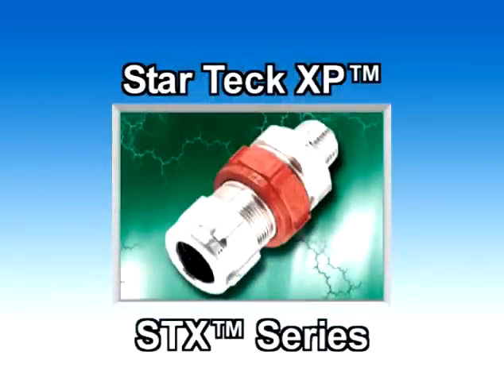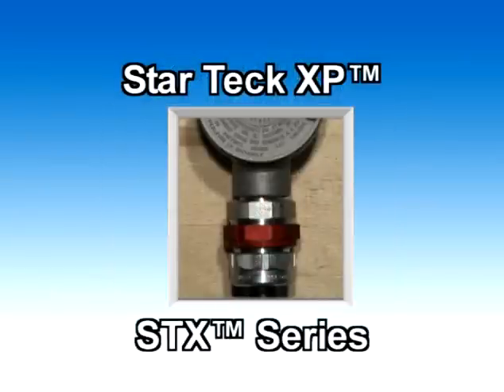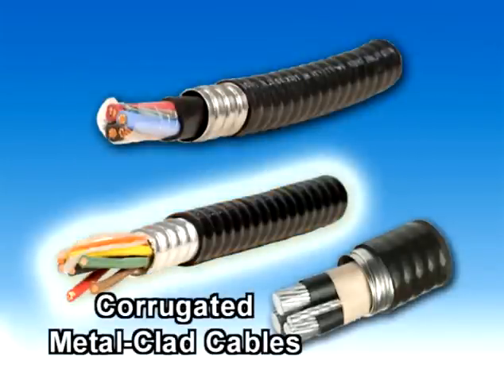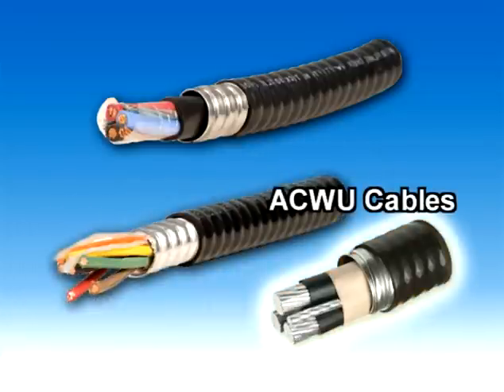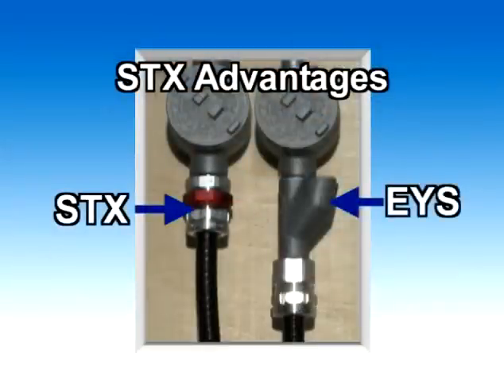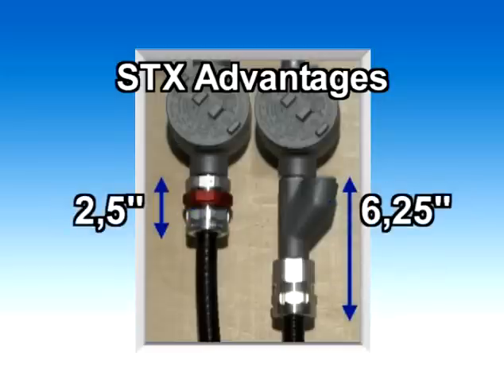Installation Methods for the Star Teck XP STX Series Explosion-Proof Cable Fitting. Star Teck XP Explosion-Proof Cable Fittings are designed for TEC cables, corrugated metal-clad cables, and ACWU cables. Installing a Star Teck XP Explosion-Proof Fitting is the same as a combined installation of an EYS with a regular TEC fitting, but takes up to three times less space.